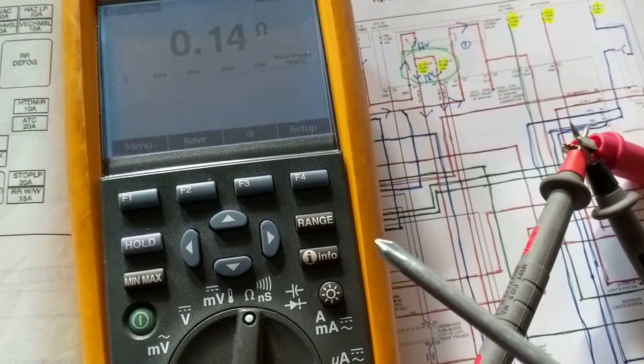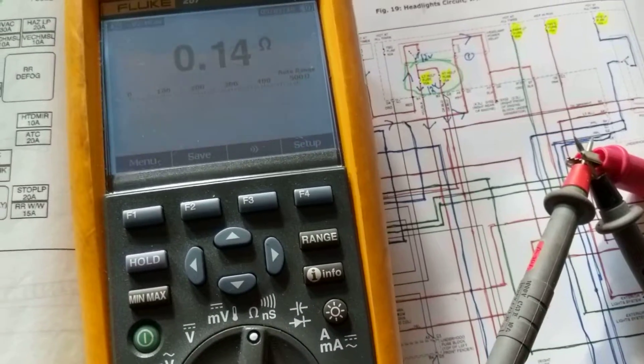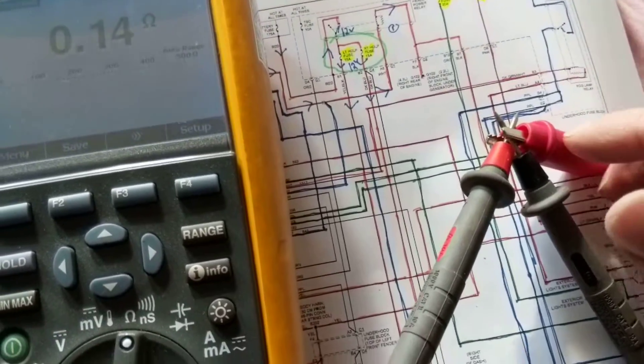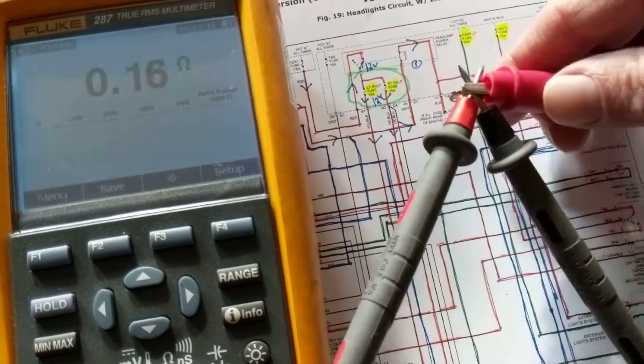You want it to measure 0.2, 0.3, not one ohm. That's way too much. So therefore always make sure the leads are shorted together. That's the first thing. Now let's take this apart.